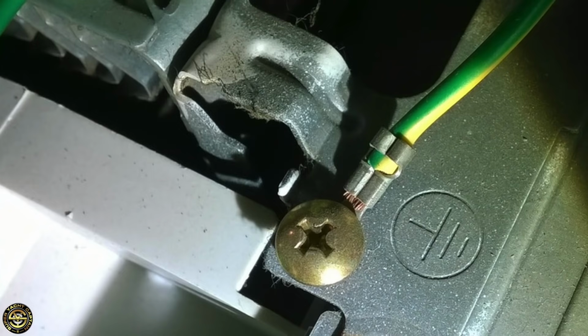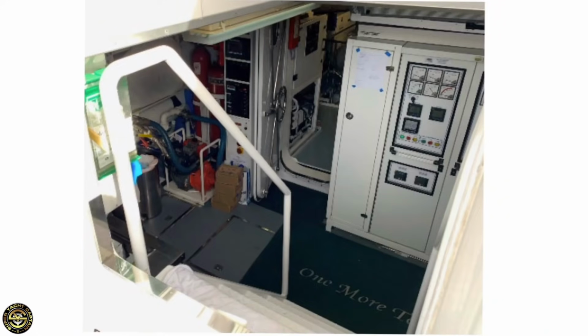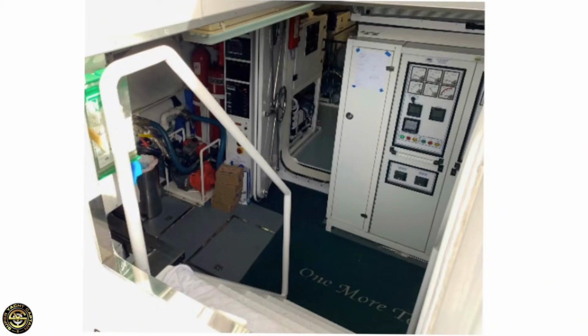The earth strap, or the earth cable that runs back to the bus bar for the outer casing, has failed or is failing. The electricity goes into the outer casing. It's alive. The whole casing is live. The unit is still running. The engineer is either standing or lying near this unit. Perhaps he's lying down on the floor, looking underneath, checking for leaks. Now, his feet are sticking out. Maybe he's touching another piece of equipment that is properly earthed. Or maybe it's just the decking, the metal decking that you often find in an engine room.